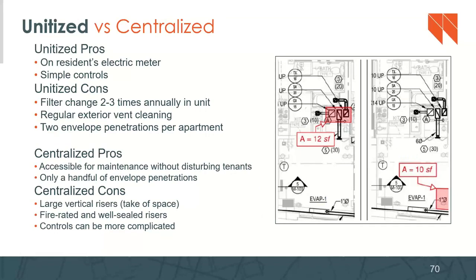Here we talked a little bit about the pros and cons of unitized versus centralized at a high level, but here are some other considerations. For the unitized pros, it can be on that residence electric meter, so the owner might not be paying for the cost of ventilation per se, because a unitized ventilator could be wired to the residence electric meter. It does have pretty simple controls. And then the cons: again, the filter change two to three times annually, if not, say, four times annually in every unit. You've got that regular exterior vent cleaning that we talked about, and of course, two envelope penetrations per apartment. You've got to be able to vent this to the outside, so those penetrations can add up quickly.